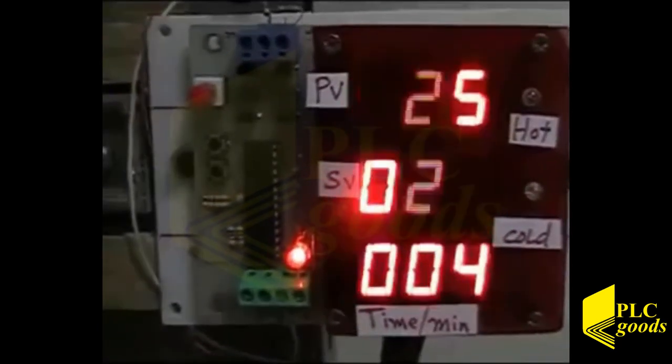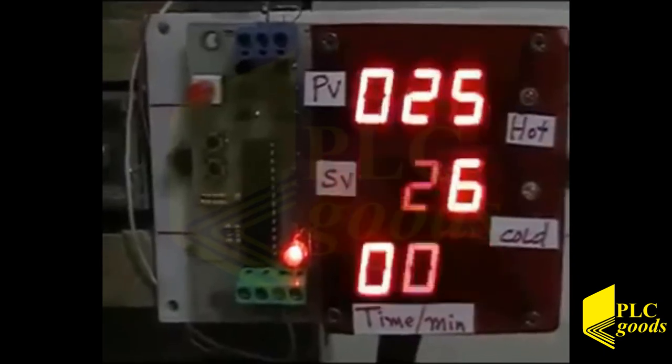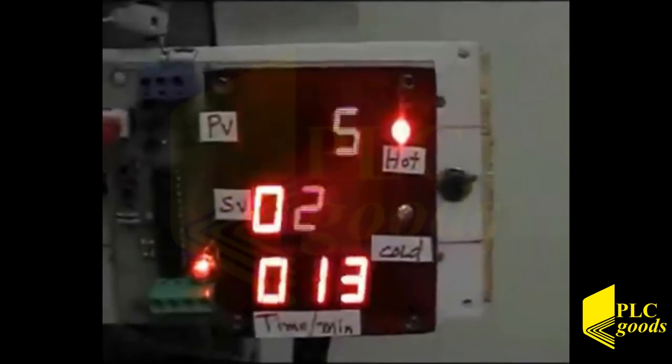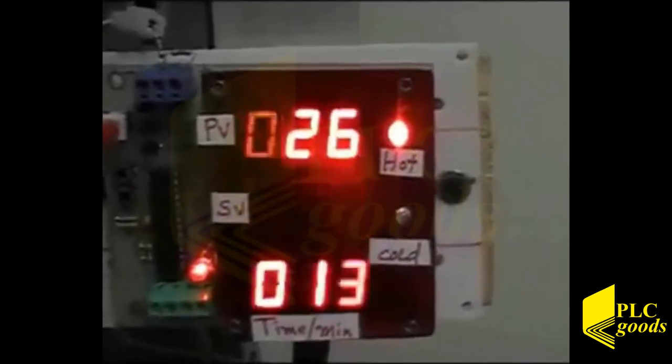Well, at time equal to 4 minutes, the difference between PV and SV is less than 3 degrees Celsius, so no need to take any action yet. Now PV value is 25 but SV value is 26.